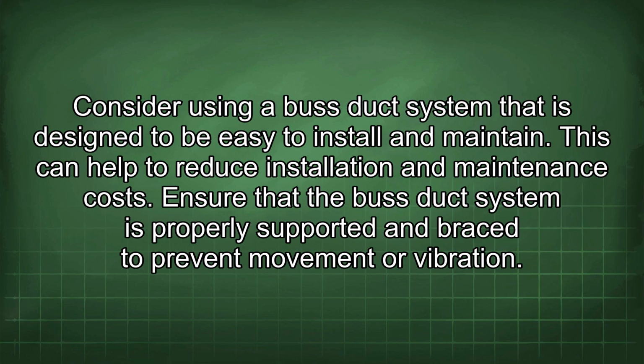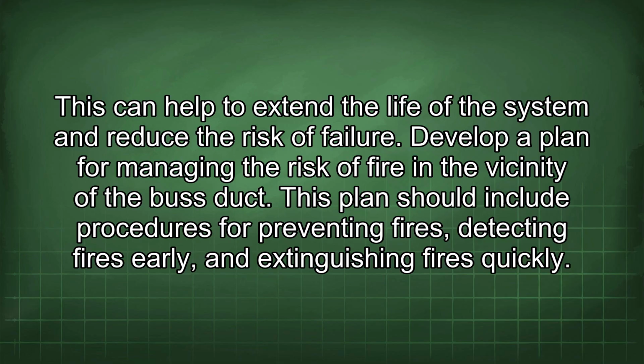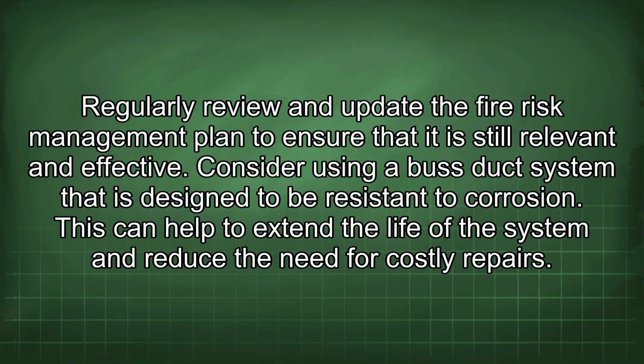Consider using a bus duct system that is designed to be easy to install and maintain. This can help to reduce installation and maintenance costs. Ensure that the bus duct system is properly supported and braced to prevent movement or vibration. This can help to extend the life of the system and reduce the risk of failure. Develop a plan for managing the risk of fire in the vicinity of the bus duct. This plan should include procedures for preventing fires, detecting fires early, and extinguishing fires quickly. Regularly review and update the fire risk management plan to ensure that it is still relevant and effective.